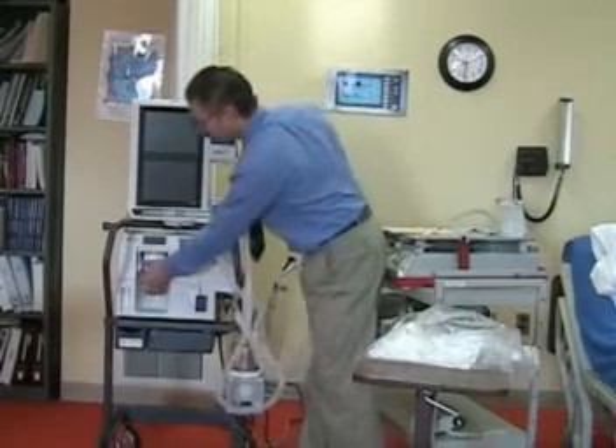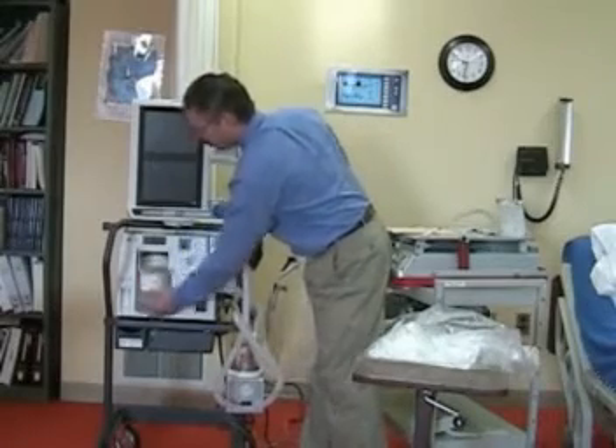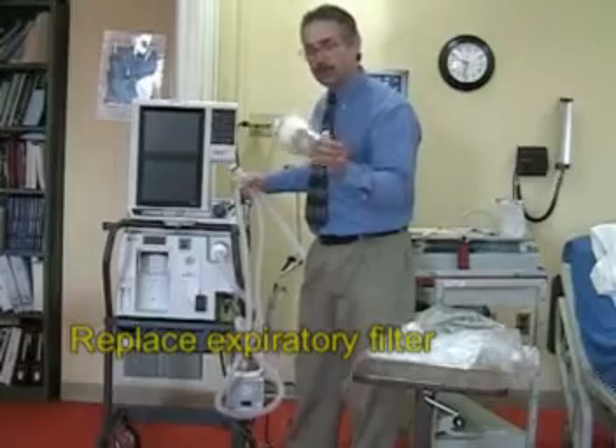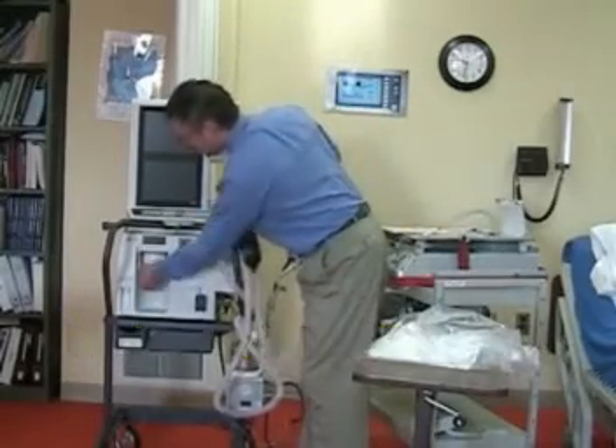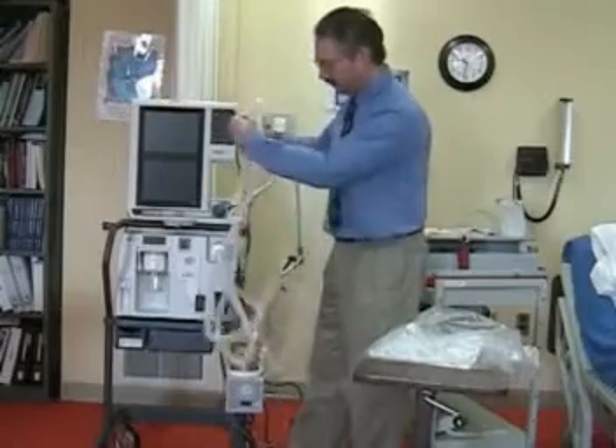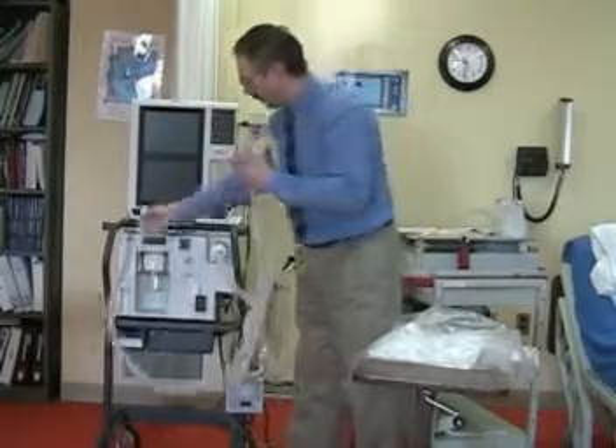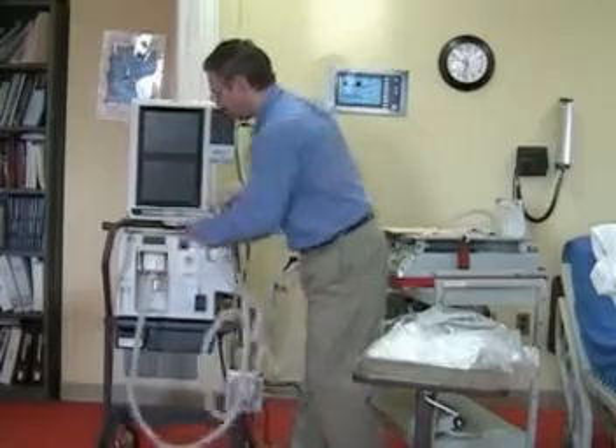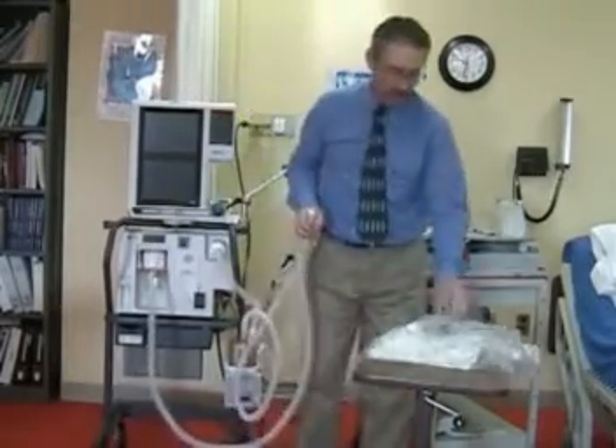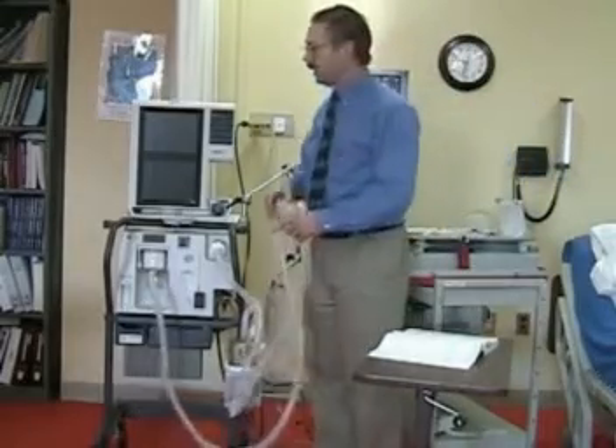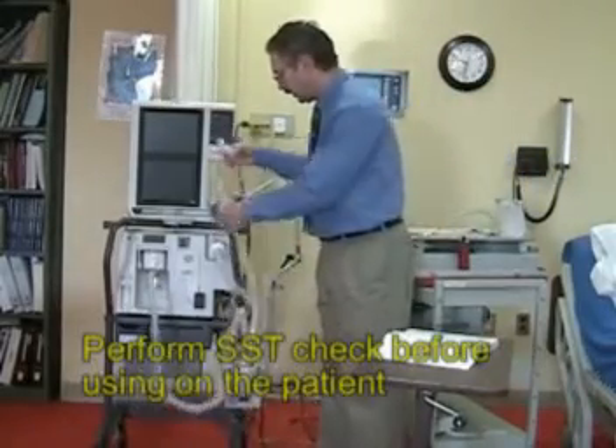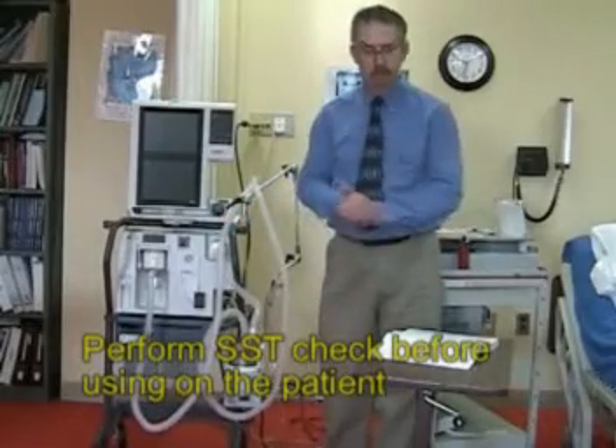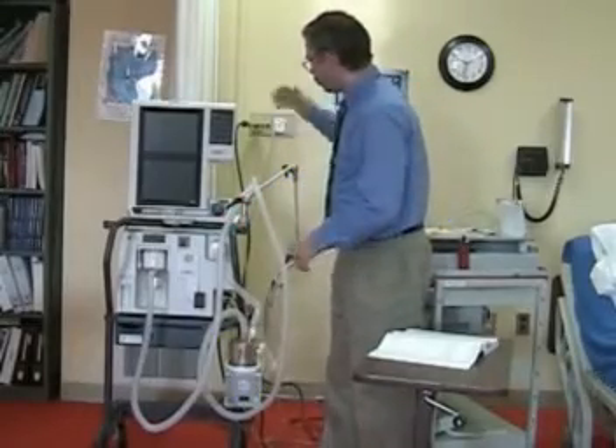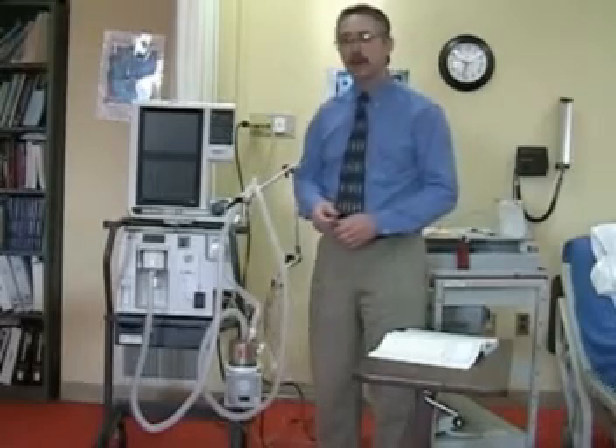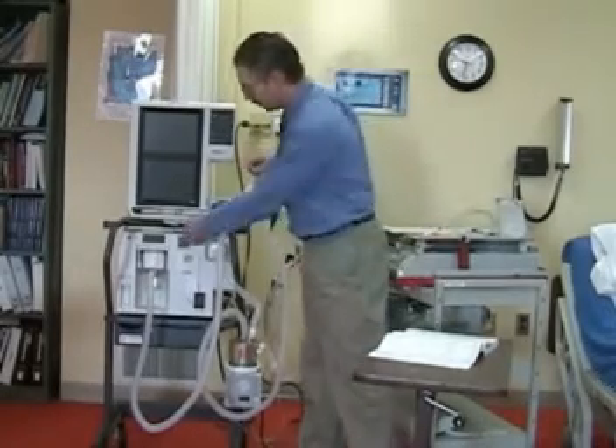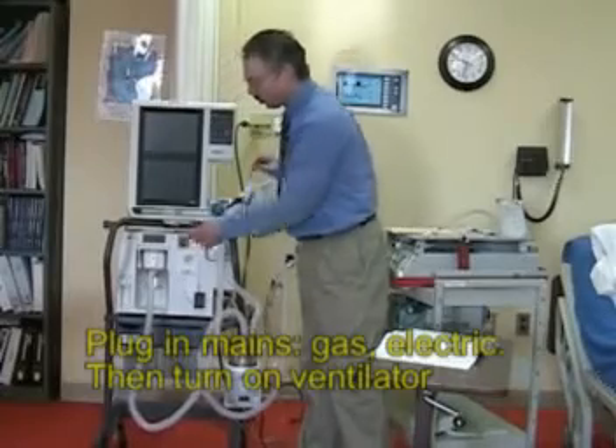And in this machine, you will want to make sure that you replace the disposable expiratory filter with a new one. Connect your expiratory line, and then you will go to the SST function of the ventilator, which is described in another section. So make sure that your gas pressure lines are connected, your power cord is in the wall outlet.